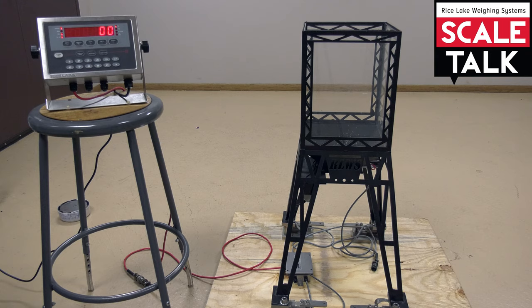Once the first calibration is done, we're then going to use material or a product to substitute for the calibration weight and then check to see if, when we add the calibration weight back to it, it's still reading the correct amount.